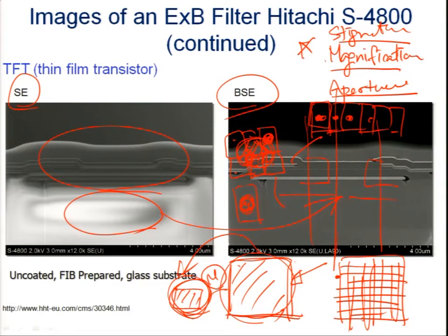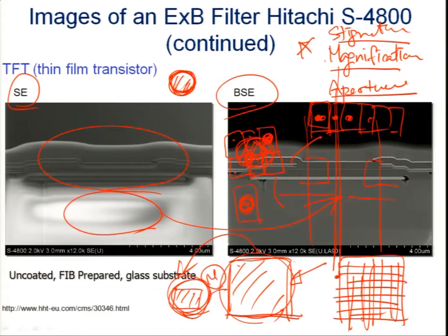If the beam axis is not aligned properly, then as we work with the focus and bring the image closer to the right focus, if the shape is a circular dot, instead of the edge of the dot just getting clearer and then blurry, the image starts to move around.